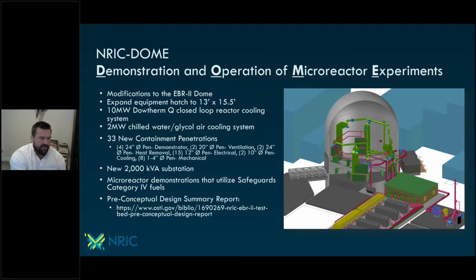The first project I'd like to talk about is the NRIC Dome. This is the project to modify the EBR2 dome at MFC to make it compatible with this test bed philosophy. There are things that need to be done, like expanding the door to get equipment in and out of the dome. There's a closed loop Dowtherm Q cooling loop that we would install, and a 2 megawatt water glycol air cooling system to control the dome atmospheric temperature. There are also a lot of different penetrations into containment needed to make it compatible with this cooling architecture and electrical, I&C, things like that. Just to power the cooling system, you need a new substation right there at the site: a small 2000 kVA transformer located there to step down the higher voltage.